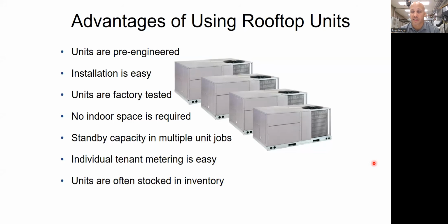And they got 6 of these things on the roof. And if one of those goes down, they still have 5/6 of their capacity. Obviously, if you have one small unit serving one little office area, then you don't have that redundancy. But on bigger open spaces, you do. On some spaces, like say strip malls, for example, they like to use these because every individual tenant can have all their own stuff. They have their own electric meter, their own gas meter, their own packaged rooftop unit, and it just serves this Subway restaurant. And this one just serves the dry cleaner, and this one just serves the nail salon, et cetera, et cetera.